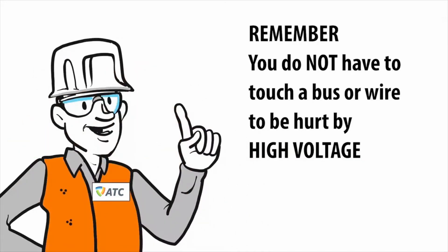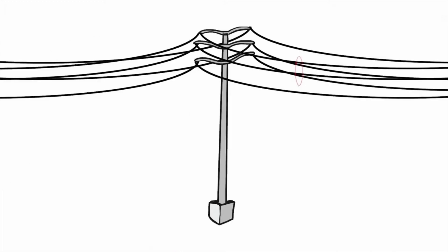Remember, you do not have to touch a bus or wire to be hurt by high-voltage electricity. That's because energy radiates around high-voltage buses and wires. Get close enough, and electricity may arc from the wire or bus to your body. The higher the voltage, the farther the electricity can arc.